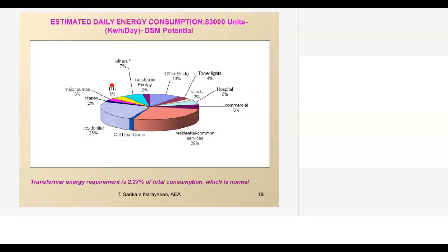See, this is a case. If you go by the energy usage data, daily 80,000 units, 83,000 units they are consuming. But a colony being a very big load, more than 28% is the residential common services. Then there is residential service, so almost 50% of the load goes towards the colony area. If such a situation arises, sometimes this percentage can change, maybe 10 or 12%. Then one has to consider what DSM option we can go for in the common services.